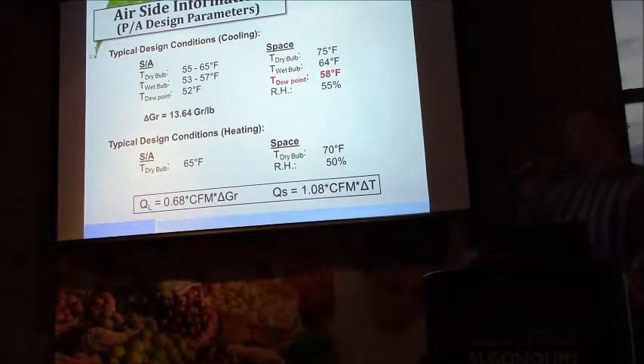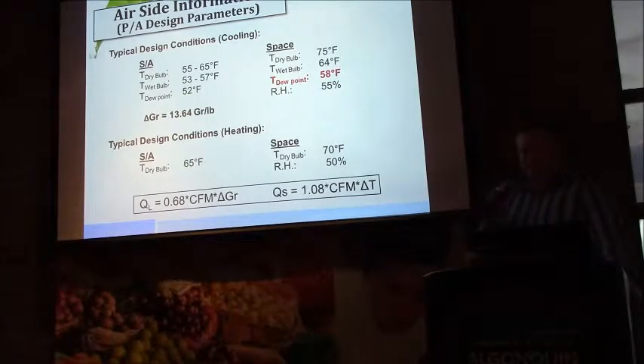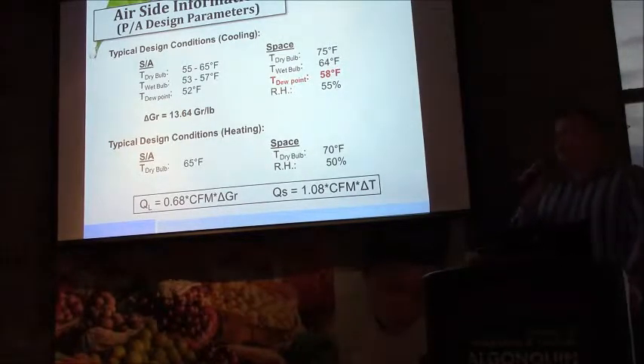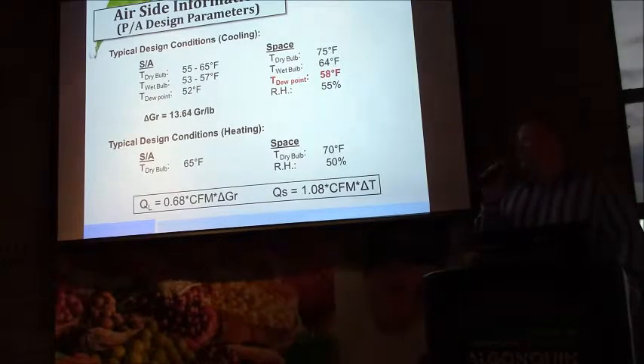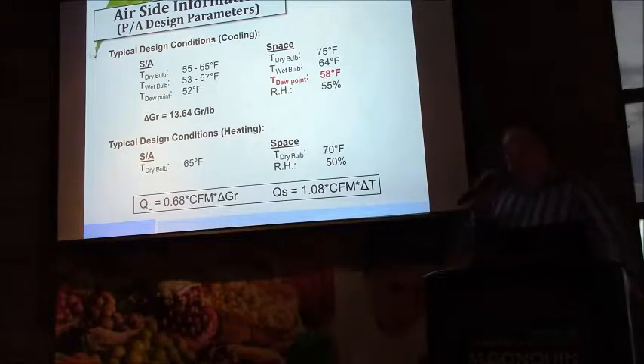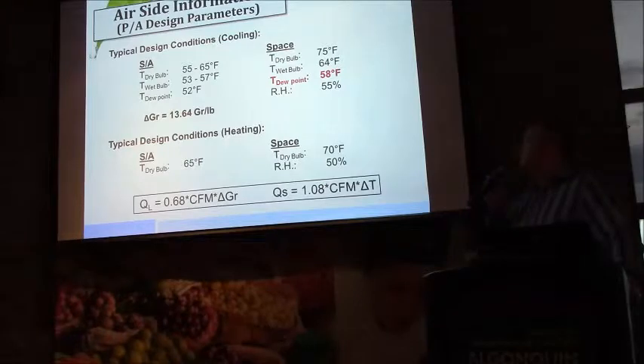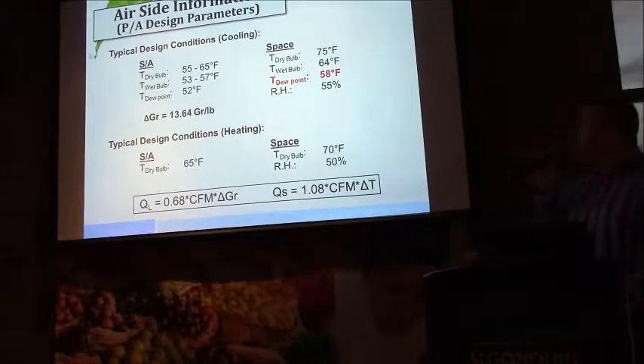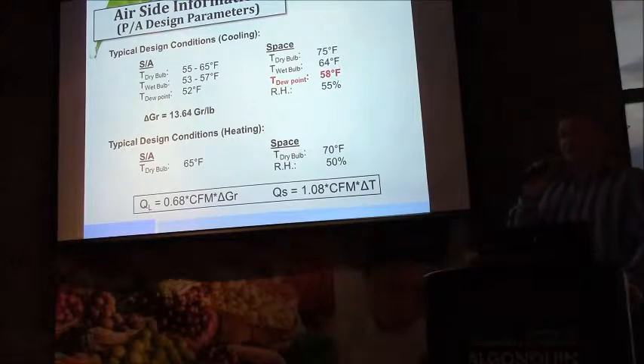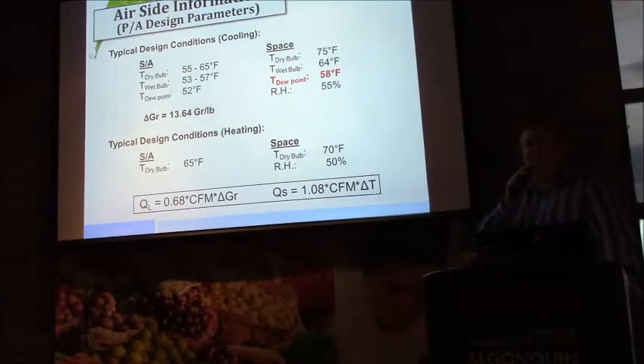These are some sample operating conditions that you might see in an active beam solution. Again, there's a range of dry bulb temperatures because of the mixing within the beam body, and it becomes less critical to the performance of the beam, but it is a contribution to the space that allows us to deduct it from the total sensible load that the beam would need to be selected to achieve that cooling. Some sample dew point temperatures that we might see off of the primary air handling unit are summarized here, along with some conditions that we might consider for the space. It's remarkable, and pretty easy to see on a psychrometric chart, that lowering the relative humidity in the space from as little as 55%, as presented in this case, to say 50%, could translate into an increase in primary air consumed by the occupied zone of as much as 30 to 40%, which is significant, obviously.